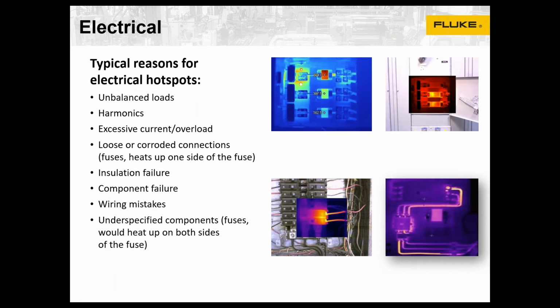A wide variety of applications. Electrical problems are probably the most commonly known for infrared. If you have any kind of a background in electrical systems, you know what generates heat. You can use that knowledge and apply that to the image to tell you what could be going on. So things like unbalanced loads, or maybe hot connections. Here's a nice example of a single phase condition, for example. You can look at that, and that can actually be a diagnostic image for you to tell you really what is wrong, so we know how to take corrective action.